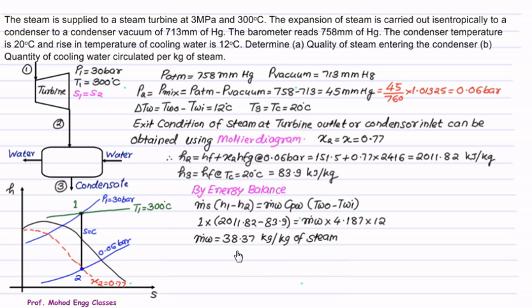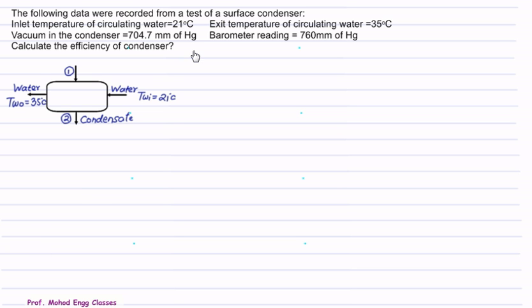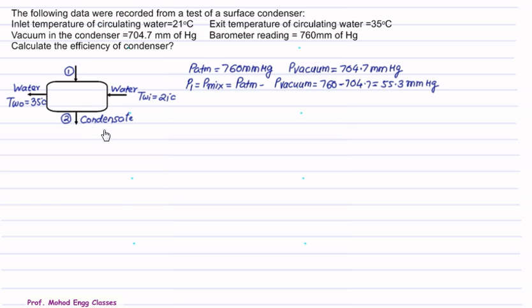In question 4, the inlet temperature of circulating water is 21°C (TWI) and the exit temperature of water is 35°C (TWO). The vacuum inside the condenser is 704.7 mm of Hg and the local atmospheric pressure is 760 mm of Hg. We need to calculate the efficiency of the condenser. First, we find the condenser pressure: P_mix = P_atmospheric − P_vacuum = 760 − 704.7 = 55.3 mm of Hg.